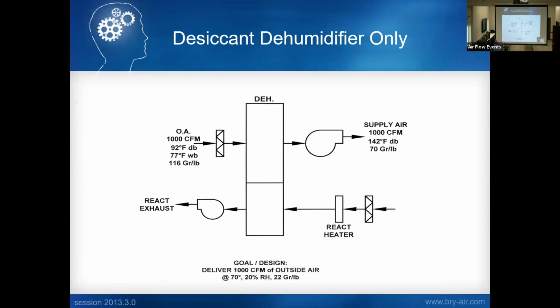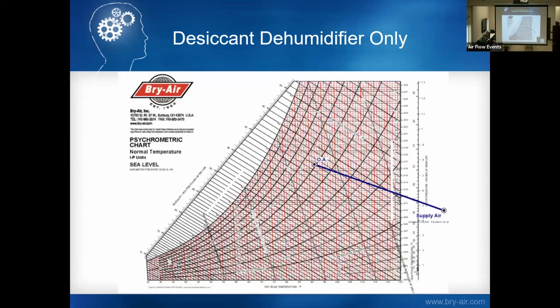Now we look at just the desiccant rotor itself, no cooling at all. Again, same goal to get down to 70 degrees, 20% RH. You can see, as we talked about earlier, I'm picking up temperature across the desiccant rotor and dropping off moisture. So with just the desiccant rotor itself, I'm able to get down to 70 grains, based on 100% outside air of 1,000 CFM. You see that on that psych chart as well.